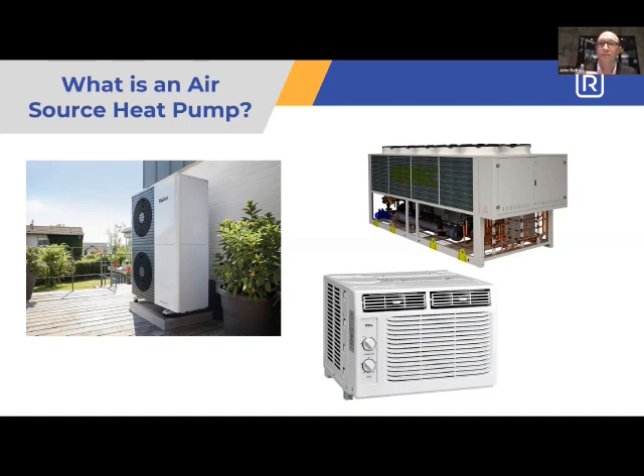There are some really great manufacturers out there that make some really highly efficient heat pumps that are able to get COPs greater than 3. And there's a ton of engineering that goes into optimizing and trying to improve the efficiency and performance of these heat pumps. But the number one factor that can determine if a heat pump is going to be efficient or not, or to improve the efficiency of the heat pump and jack that COP as high as possible, has nothing to do with the heat pump itself, and it has everything to do with the temperature of the source. So in this case, air.